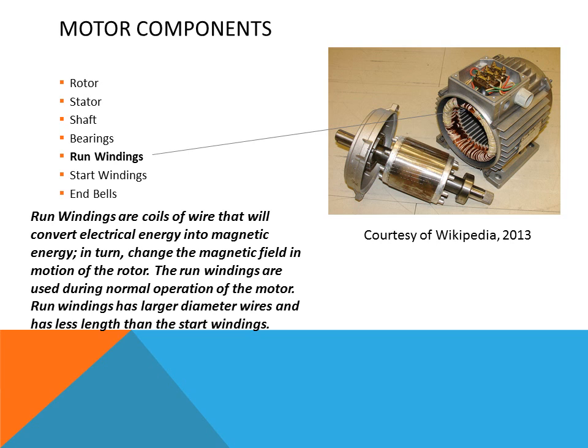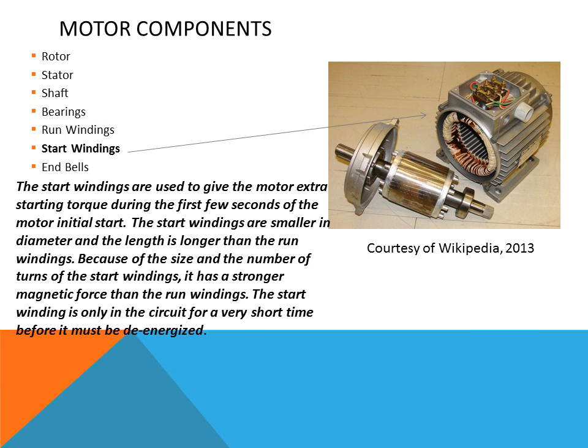The run windings are the main windings of a motor — they do the work while the motor is operating and have a strong magnetic field to keep the rotor in motion. The start windings are the secondary windings, used only for a very short time at the initial start of a motor. The start windings receive voltage only during startup, then come out of the circuit. If they did not come out, the motor would overheat and trip on thermal overload. The start windings have more turns than the run windings, giving them an extremely high magnetic field to get the rotor moving.